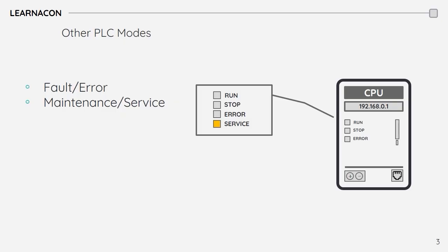The reason is that the PLC components, like every other piece of electronic hardware these days, are equipped with firmware or operating system, which is typically updated every 6 months. So you need to make sure that the configured application is in line with the hardware you are using. Otherwise, the CPU detects the mismatch and switches to service mode to avoid any unwanted behavior. Most of the time, you can solve the service mode issue simply by updating the firmware.